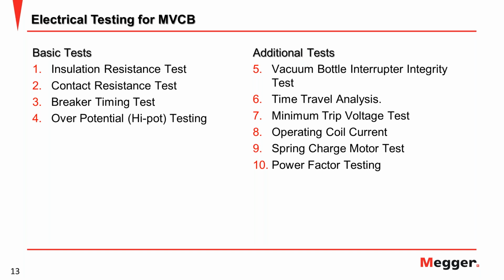Okay, now we'll go to the main topic, the electrical testing for medium voltage circuit breakers. There are many tests to be done actually, but there are two types, basic tests and additional tests. You can find these tests in some standards, but mostly these four basic tests you can find in all international standards: insulation resistance test, contact resistance test, breaker timing test, and also over potential. I mean, it is the hipot testing.